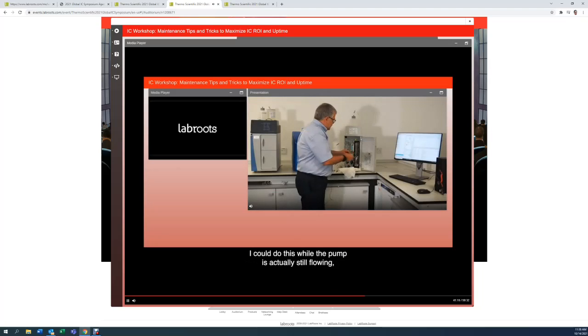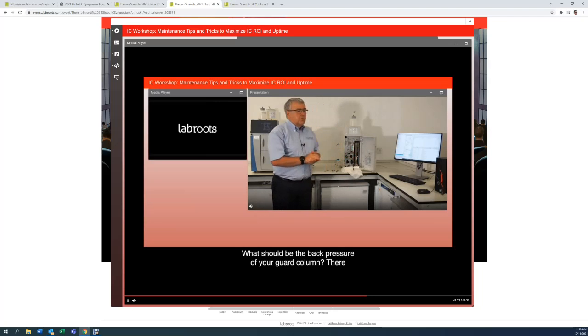What I'm going to do now, and I can do this while the pump's actually still flowing, is introduce the guard column. There we go. And we'll watch the pressure build. Now then, what should be the back pressure of your guard column? There is no test chromatogram that comes with a guard column. You can read it in the instruction manuals. But basically, a good guide is the test chromatogram that comes with the analytical column, this one here. The back pressure of a guard column is around about a third, maybe a quarter of the back pressure of your separator column.